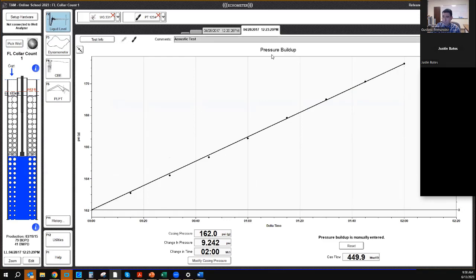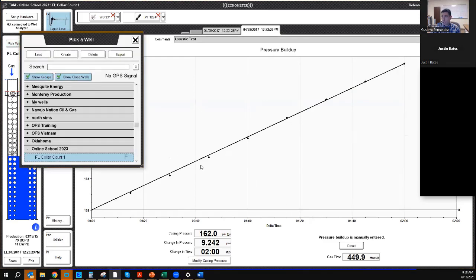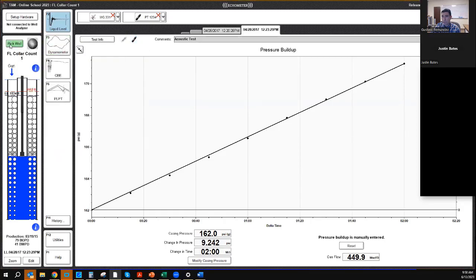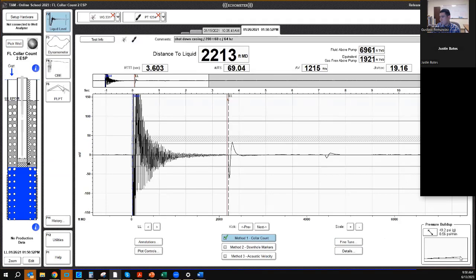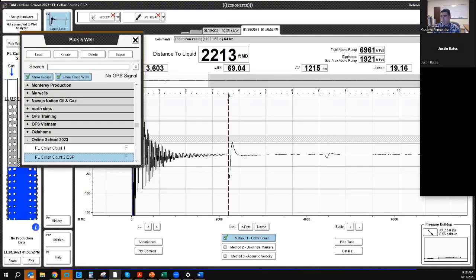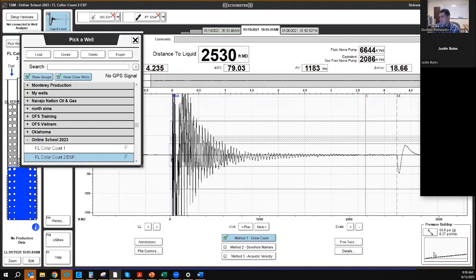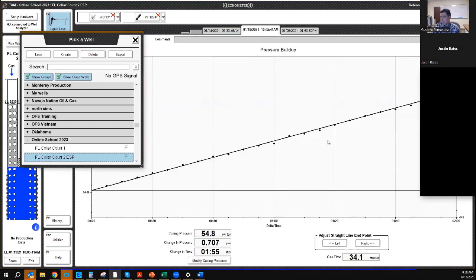It doesn't have to go building up, but it has to be linear. So most of the pressure points must remain on the same line. So we look at this trace, this is very linear too. If we look at other shots here, this is a very good pressure buildup. You see, most of the points are right on the line. And that's ideal. That's what you're expecting. If you don't have that, you have to allow the software more time.